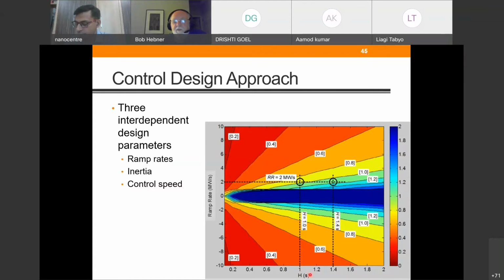If you do the stability calculations - take this example - if you have an inertia of 1 second and a ramp rate of 2 megawatts per second, your control system has to react within 1 second. If you increase the inertia a little, you can give yourself about 1.1 seconds to react. So the three things that have to interact are pretty obvious: how fast is it trying to change, how fast can I control it if it wants to change, and what's the inertia in the middle that serves as the shock absorber?